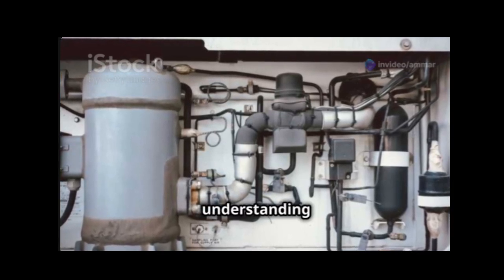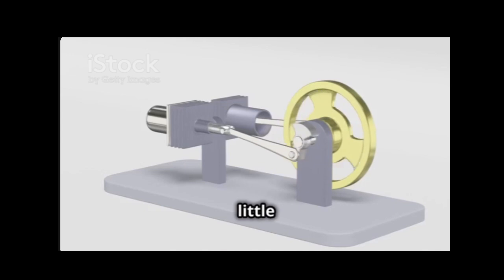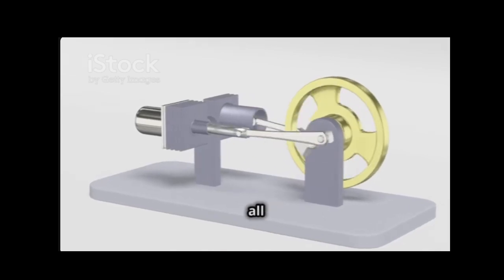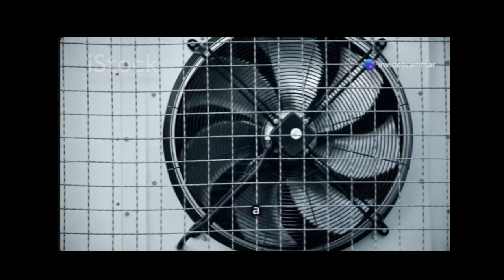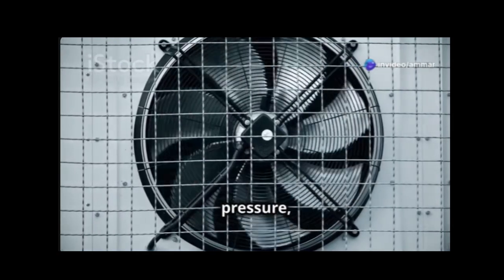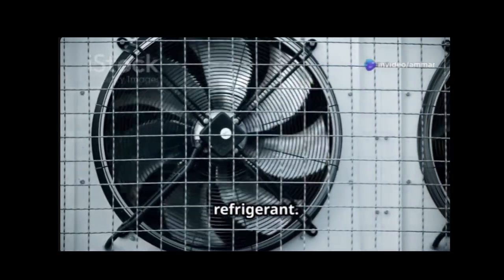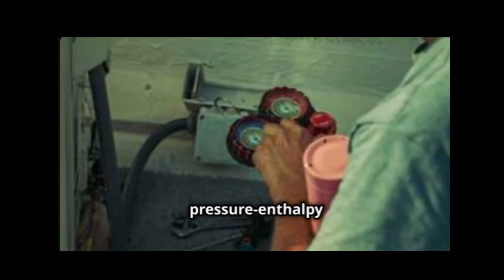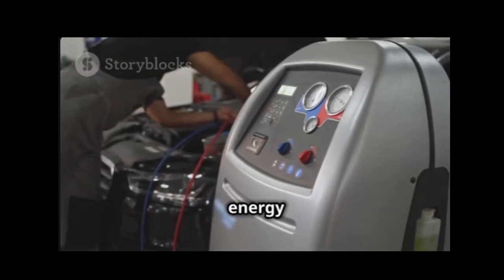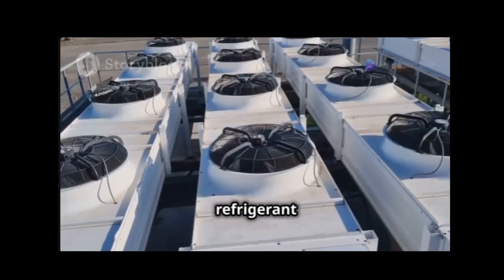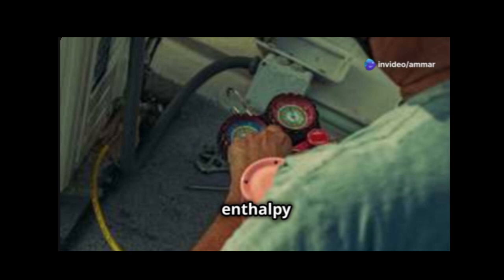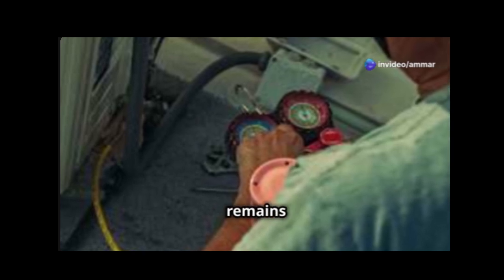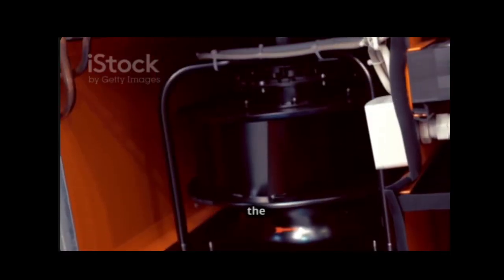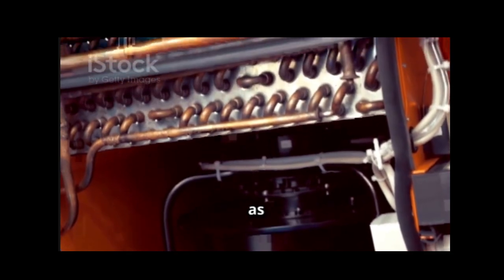Now that we have a basic understanding of the components involved, let's dive a little deeper into the thermodynamic cycle that makes it all possible. The refrigeration cycle is a continuous loop that involves changes in pressure, temperature, and state of the refrigerant. We can visualize this cycle on a pressure enthalpy diagram, which helps us understand the energy changes taking place. As the refrigerant absorbs heat in the evaporator, its enthalpy increases, but its pressure remains relatively constant. In the compressor, the refrigerant's pressure and enthalpy both increase as it's compressed.